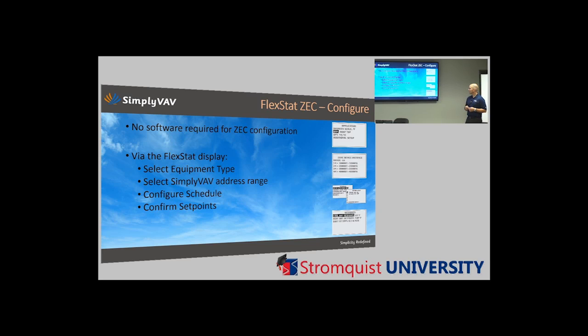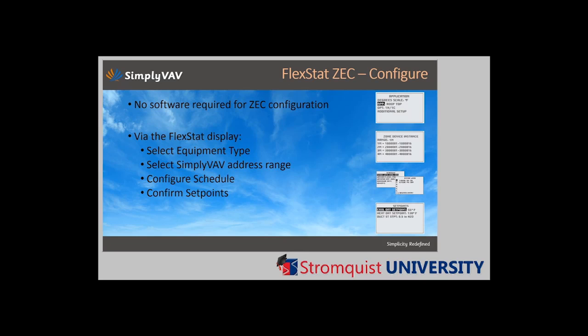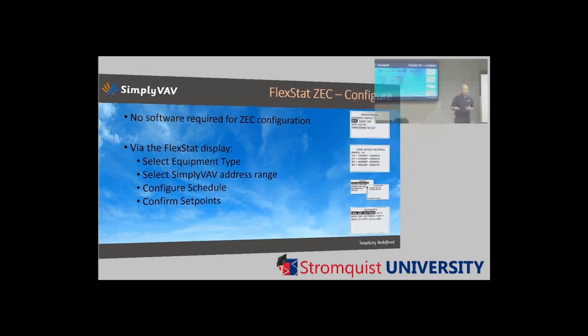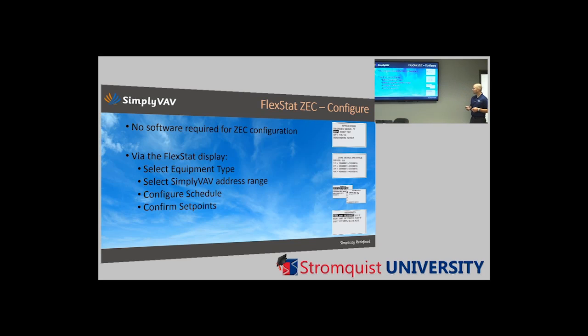So the steps you would need to set up a zoning controller would be select your equipment type, rooftop or heat pump, one stage, two stage, three stage, etc. You're going to select what address range, what BACnet instance range is going to be pulled for that zone demand. You can configure a schedule as 5 and 2, 5, 1 and 1, individual days, or with holiday exceptions. And then you're going to just confirm your DAT set points. Defaults are 55 and 130, but they could be adjusted to whatever the job spec needed. And you're done.